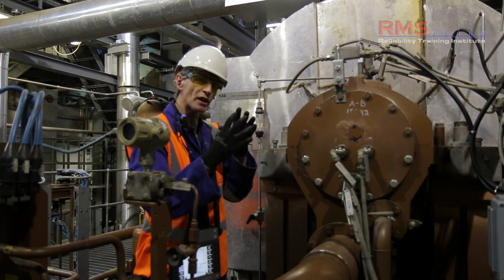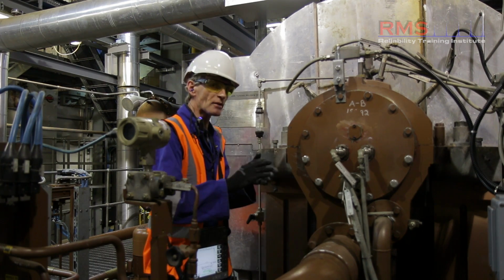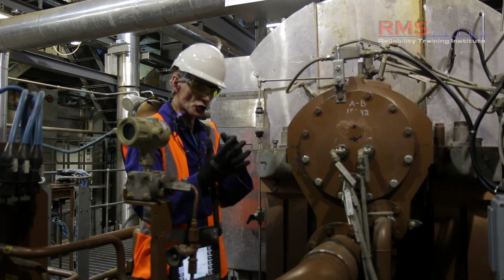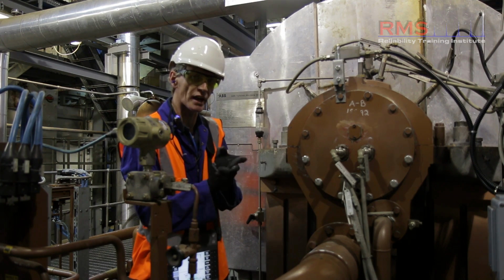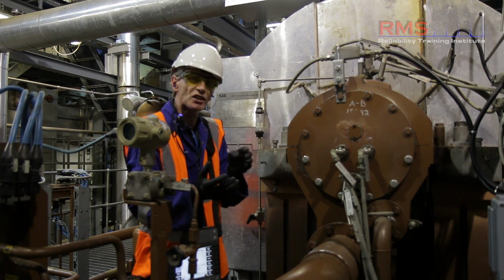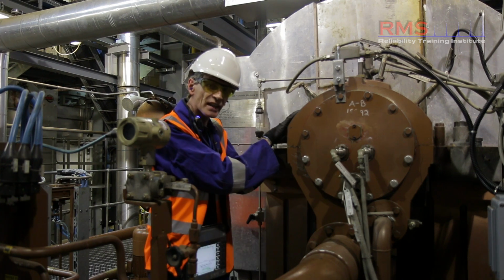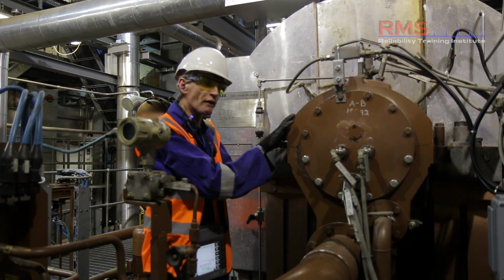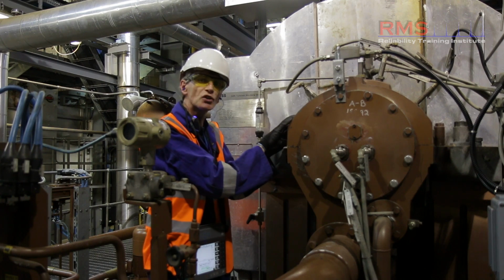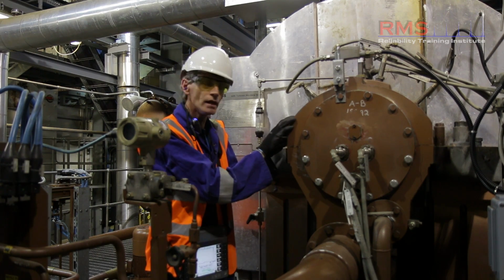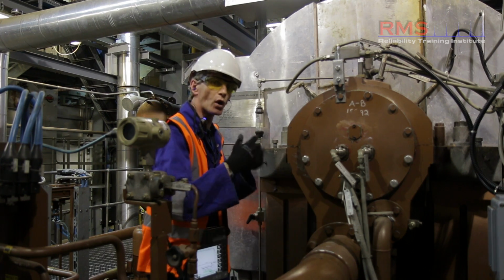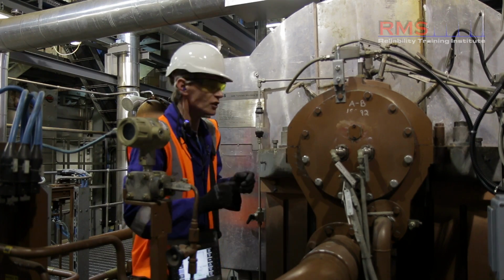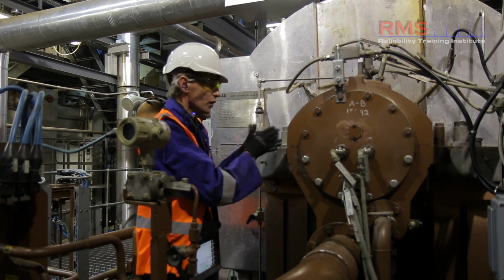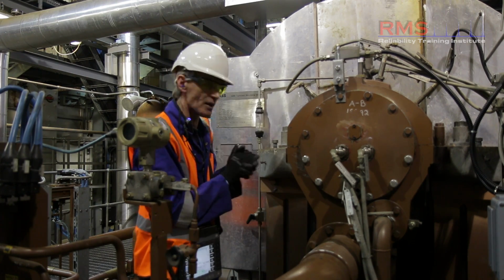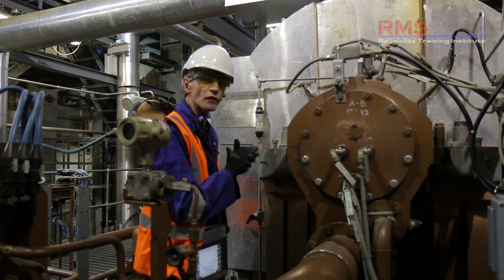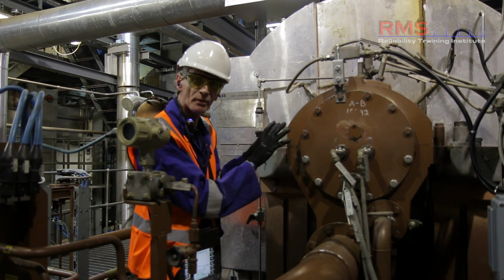Now, we have machine protection and we have machine prediction. We're going to just talk about the machine prediction side of things, where initially we're going to take some measurements on the casing of the bearing, but it's very important to appreciate that we also need to measure dynamically the probes themselves. We'll look at that a little bit later on. So initially I'm just going to show you taking my measurements in 3 axes on the sleeve bearing at the non-drive end of the high pressure end of the turbine.